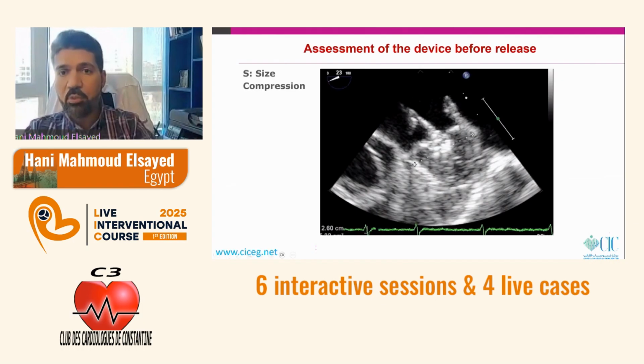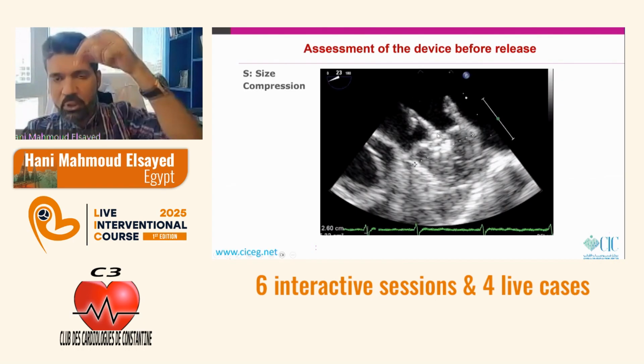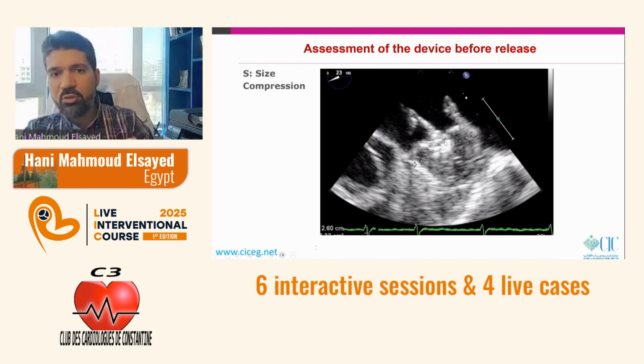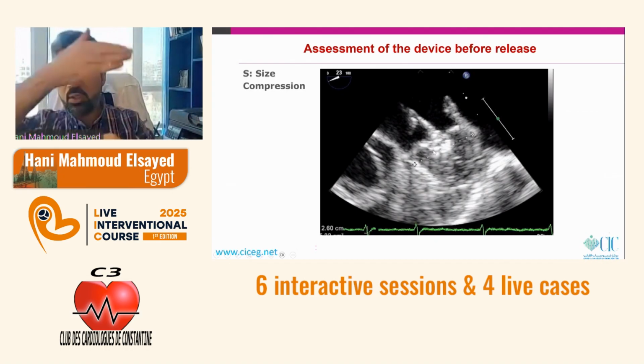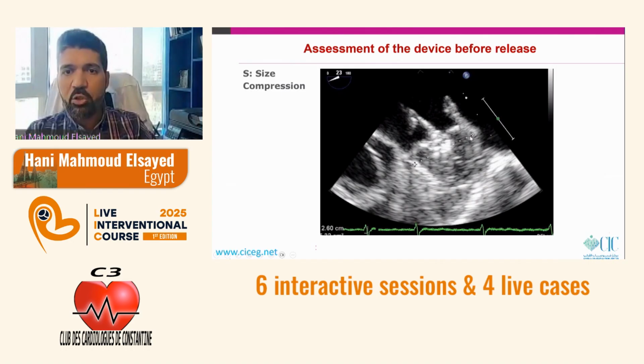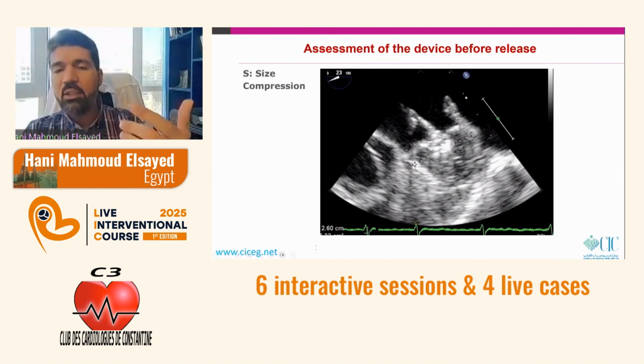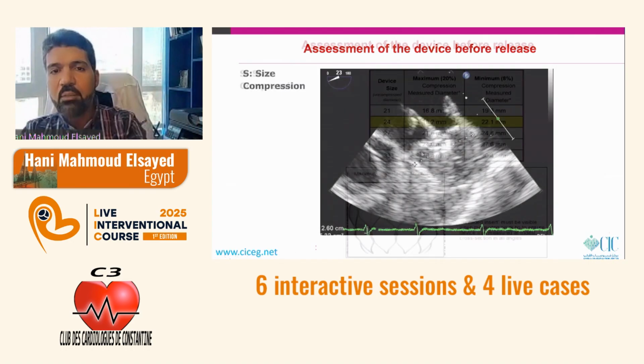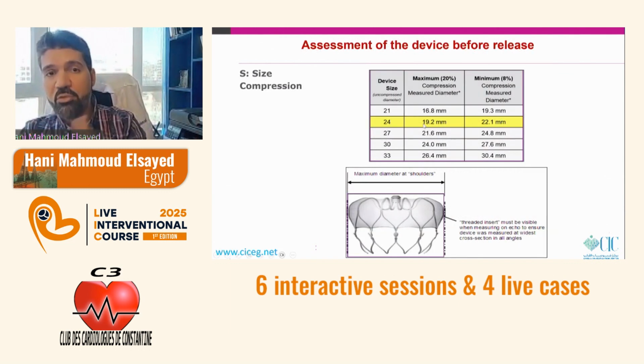The size, the compression, you have to get a view to see the knob, the middle knob of the device, and then you have to see the two shoulders. That means you are right in the middle of the device. And then you measure from here to here, and then you compare that with the previous dimension of the device. For example, if the device was 24 uncompressed, you have to see this dimension inside the body between 19 and 22. It has to be compressed between 8% to 20%.